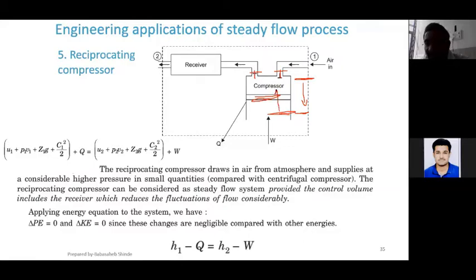in vertically upward direction. So what will happen? There will be continuous reduction in available area. The amount of air is going to remain same because both the valves are closed. So air will get compressed, and when this piston approaches this topmost position, this delivery valve will open and the compressed air will be supplied for the application purpose.